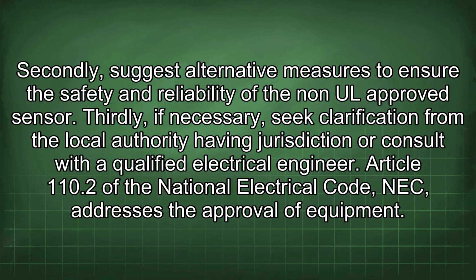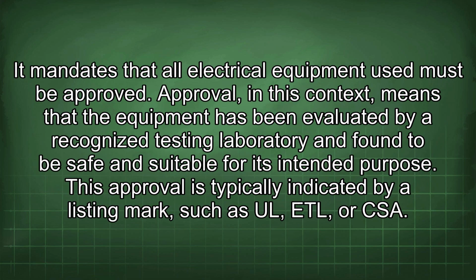Article 110.2 of the National Electrical Code, NEC, addresses the approval of equipment. It mandates that all electrical equipment used must be approved. Approval, in this context, means that the equipment has been evaluated by a recognized testing laboratory and found to be safe and suitable for its intended purpose. This approval is typically indicated by a listing mark such as UL, ETL, or CSA.